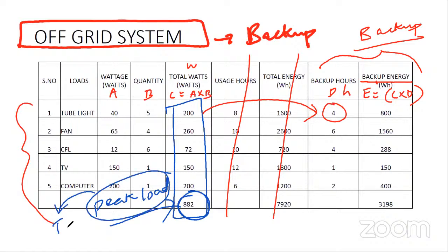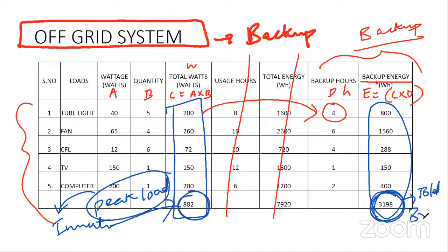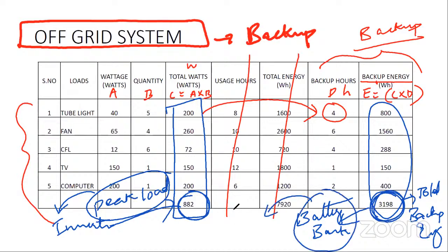This peak load decides the inverter capacity. Coming to the next, after arriving at the backup energy for all loads, this is the total backup energy. This decides the battery bank capacity. From the battery bank, we arrive at the PV array capacity.